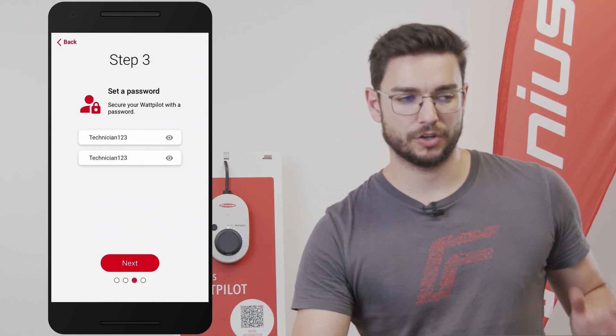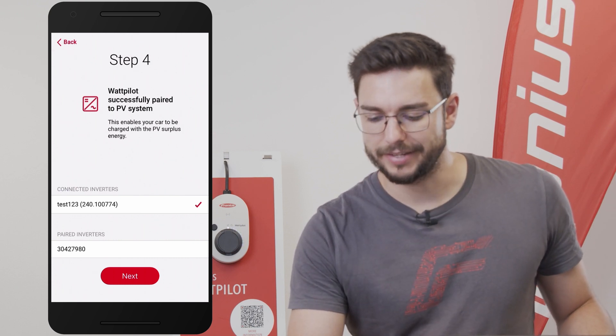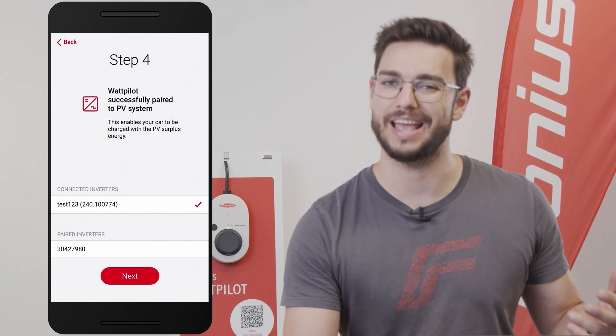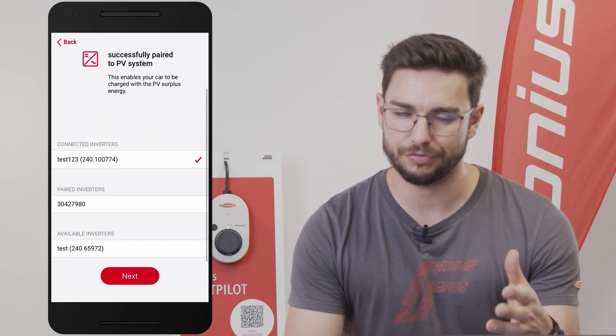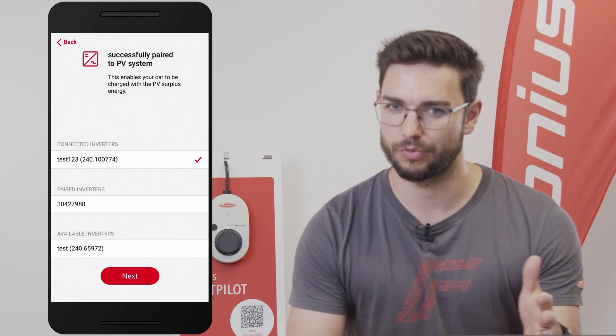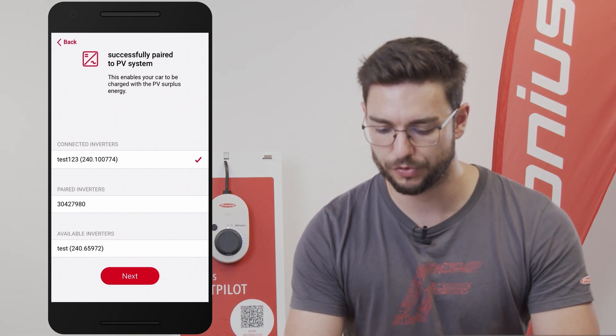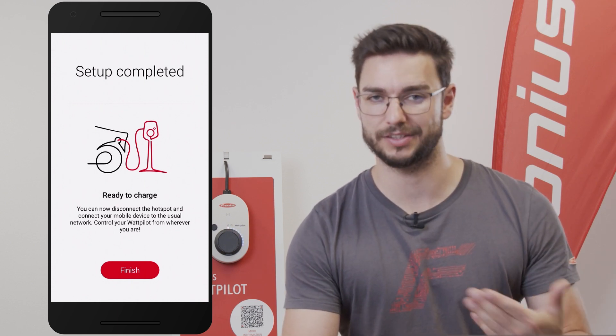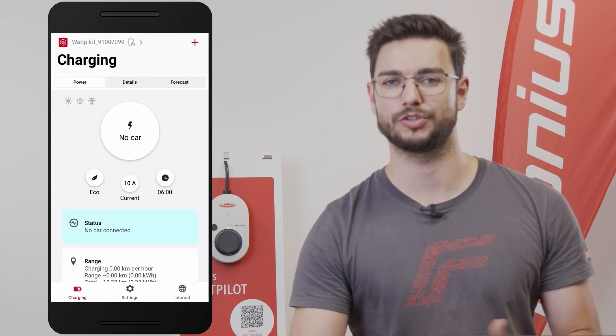After correctly selecting the password, we hit next and come to step number four, which is the final step. Here we can select an inverter if it's in the same system, in order to have the PV surplus option and the eco mode ready to use. This is only possible if you have a Fronius inverter up and running. If it's not visible here, it indicates you are on the wrong network — the inverter and Wattpilot must be on the same network to find each other. In our case we select 'Test 123' as our inverter, hit next to establish the connection, and after that the setup is completed. We hit the finish button and we are done — ready to start the charging process.